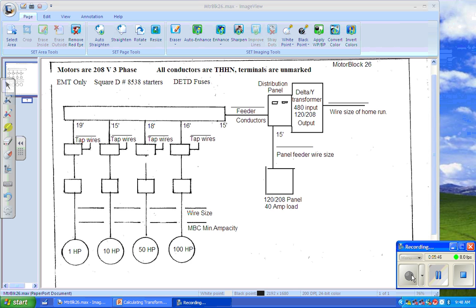Okay, look to the far left and you'll find the control circuit conductor size, and that applies to all three columns. So at the top, we have 18, and if we come back over here to where it says copper, it says 7. So what does that mean? We could have a fuse or disconnect no more than 7 amps. For 16 wires, 10 amps again.